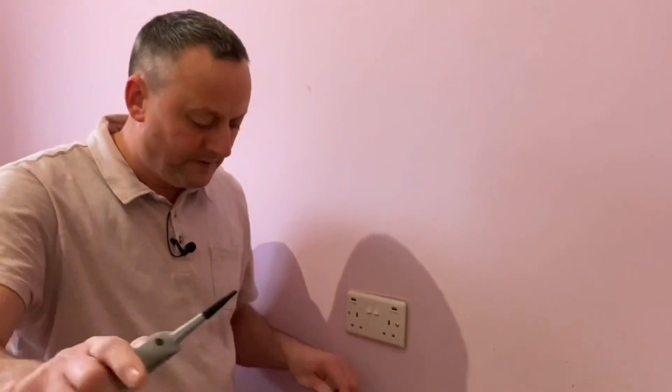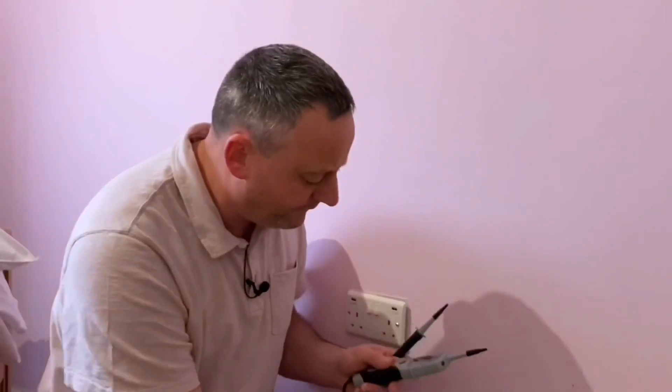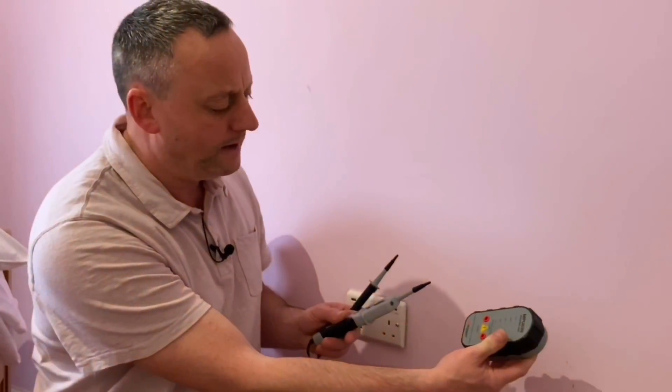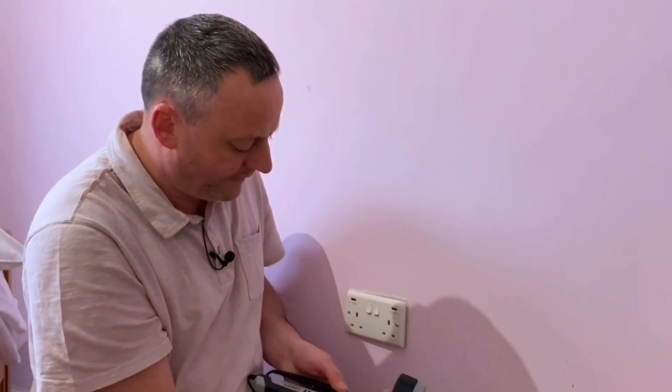So let's test this first. If we take our approved voltage indicator, we know the tips must be no greater than four mil. We've got our proven unit and I'm just going to plug it in like so and just prove that that works.